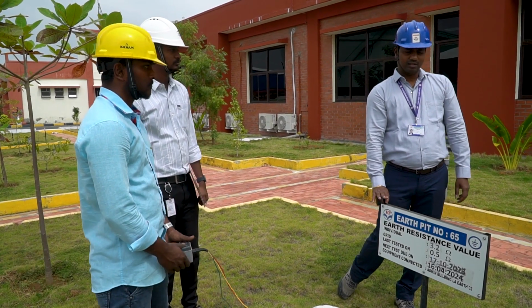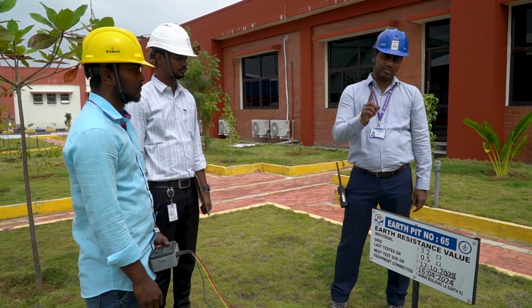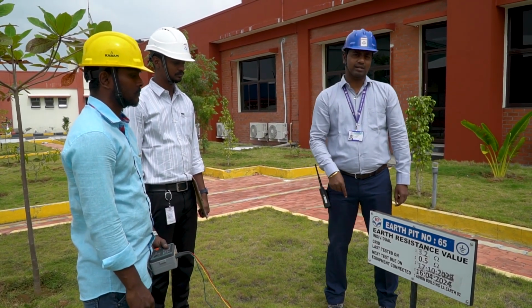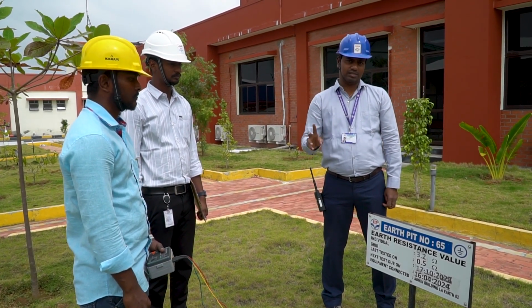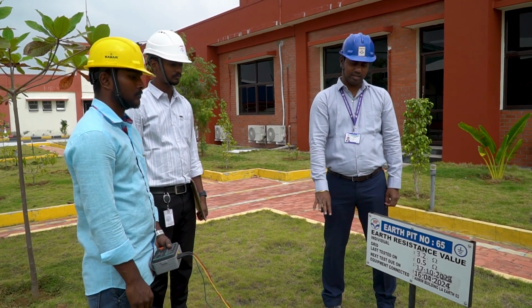Similarly, we will check all the earth pits once in 6 months. This is mandatory for all terminals, depots, plants, whatever it is. This has to be followed. Close coordination with the electrical department is mandatory, especially in case of resultant power failure at the location. I give periodic training to contractor staff on functioning and overall awareness of electrical safety.